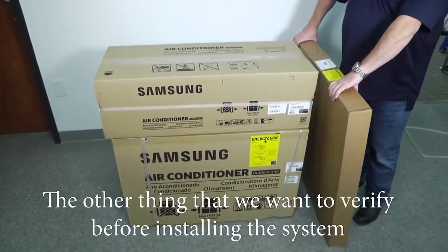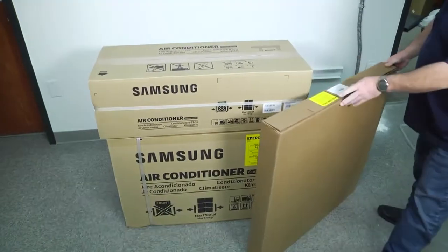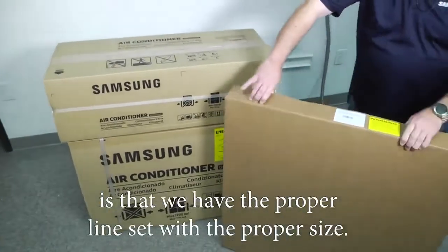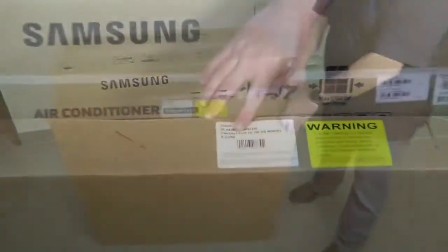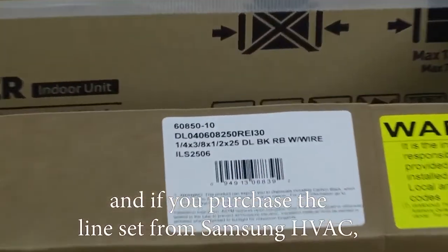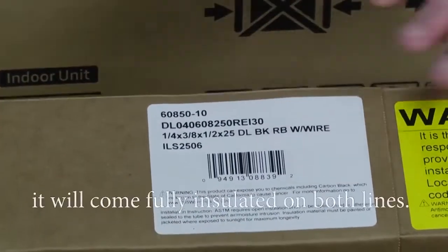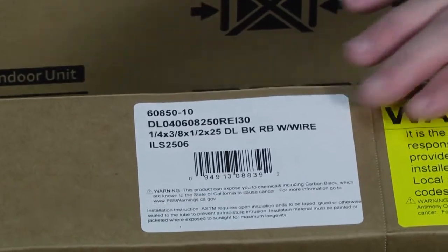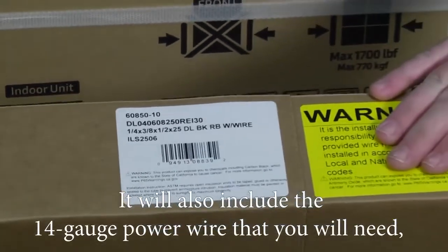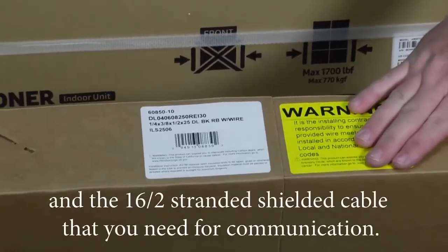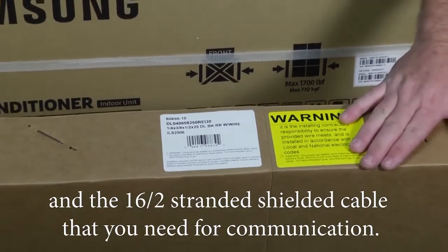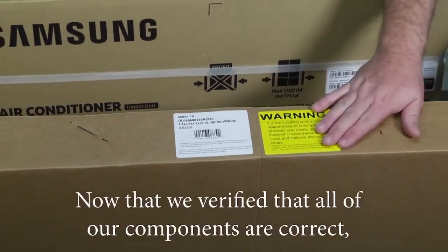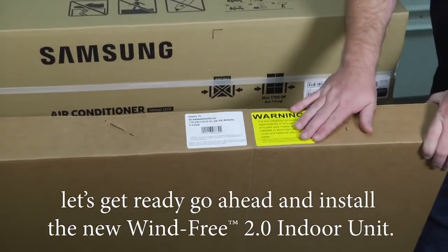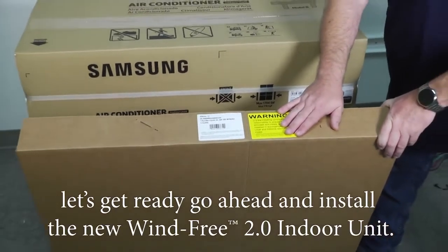The other thing that we want to verify before installing the system is that we have the proper line set with the proper size. And if you purchase the line set from Samsung HVAC, it'll come fully insulated on both lines. It'll also include the 14 gauge power wire that you need and the 16-2 stranded shielded cable that you need for communication. Now that we've verified all of our components are correct, let's get ready to go ahead and install the new Wind-Free™ 2.0 indoor unit.